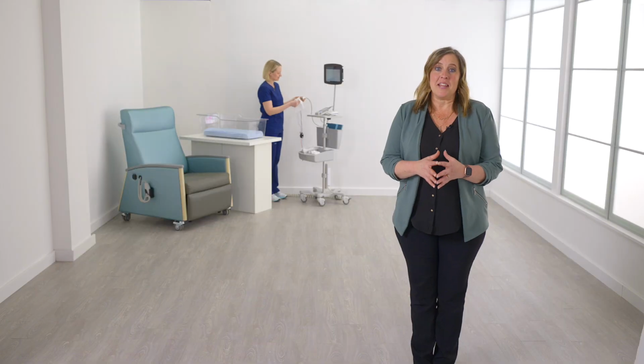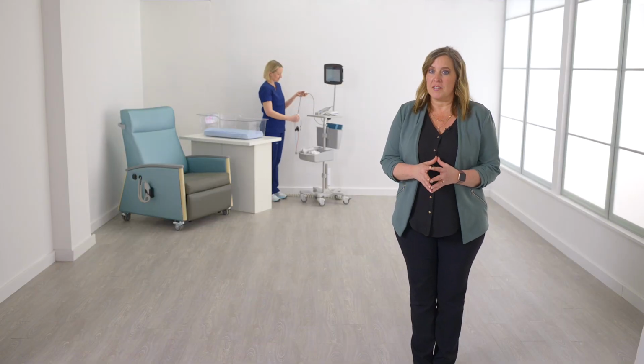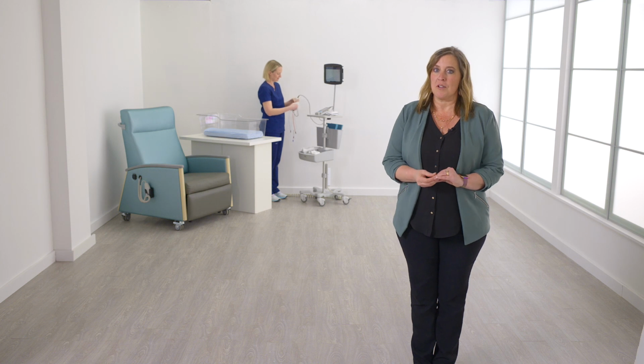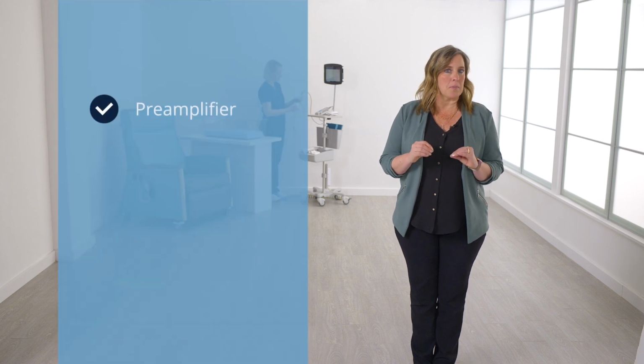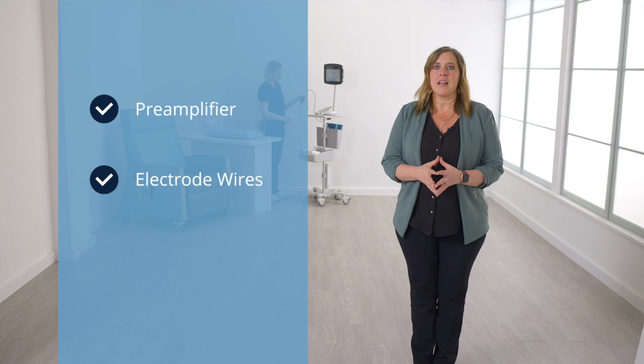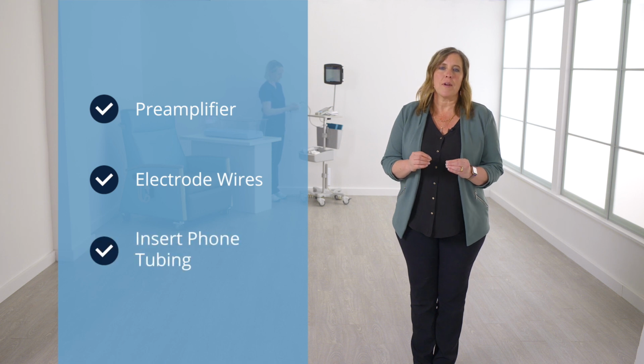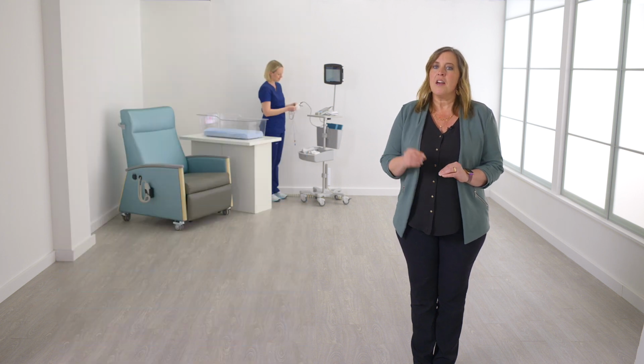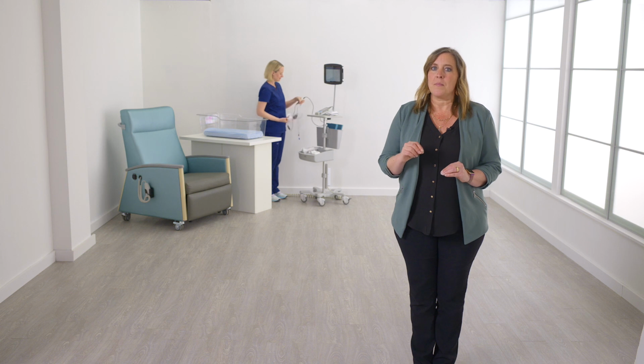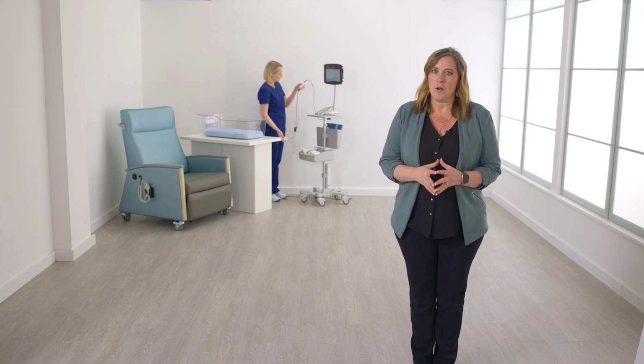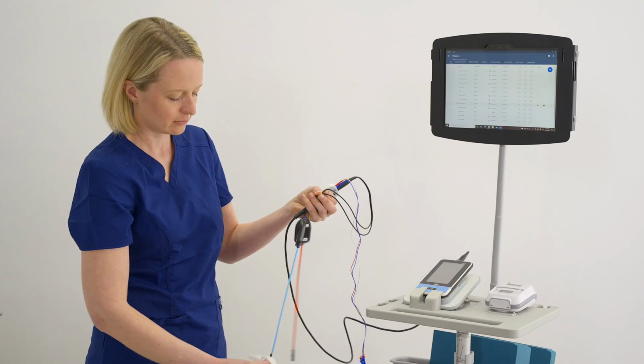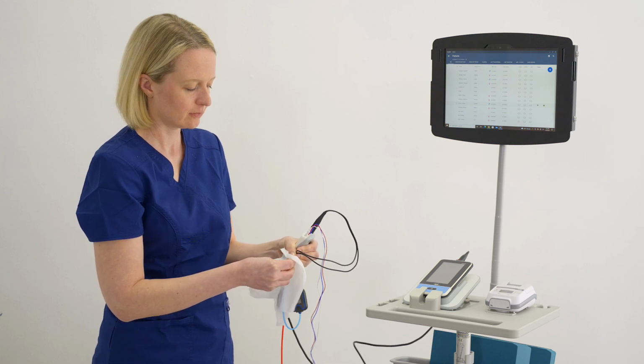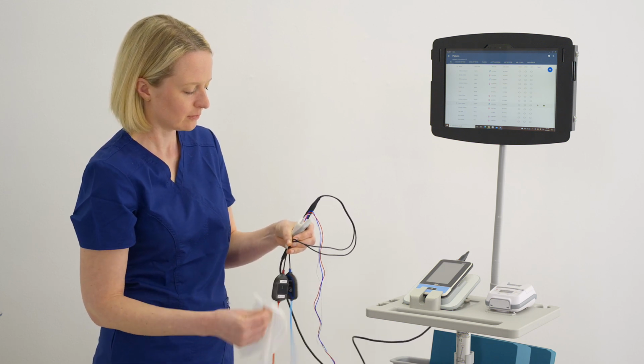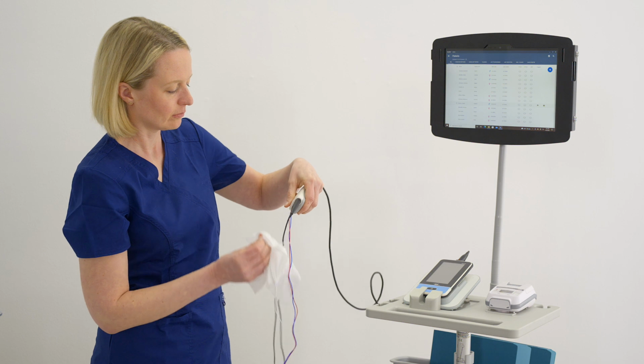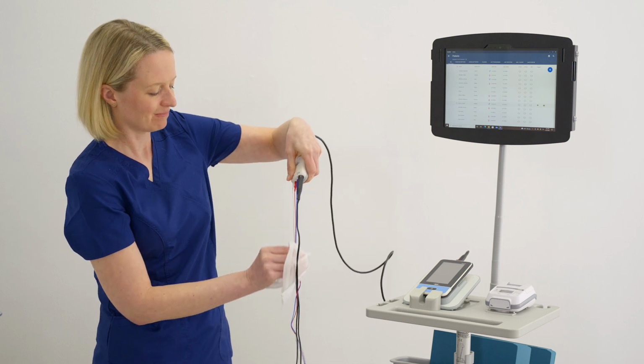It is recommended that the non-disposable parts of the Novus system be disinfected between screenings. These parts include the preamplifier, electrode wires, and insert phone tubing, which come in direct contact with the infant. Physically wipe down the equipment by using a disinfectant approved by your facility. Non-alcohol-based disinfectants that contain the active ingredient quaternary ammonium compound or a hydrogen peroxide-based cleaner may be used.